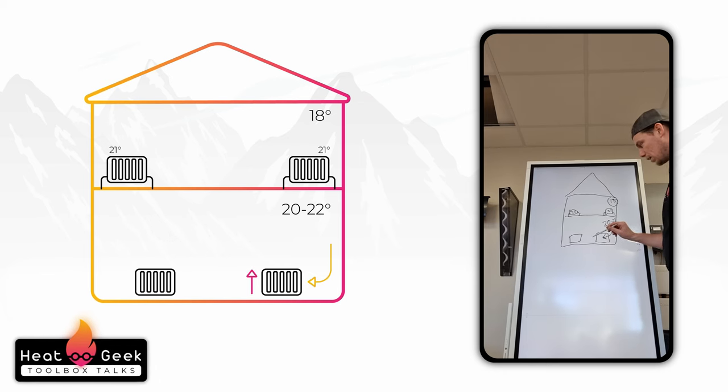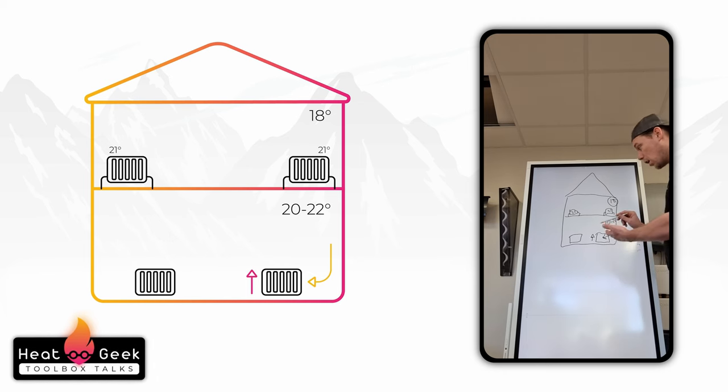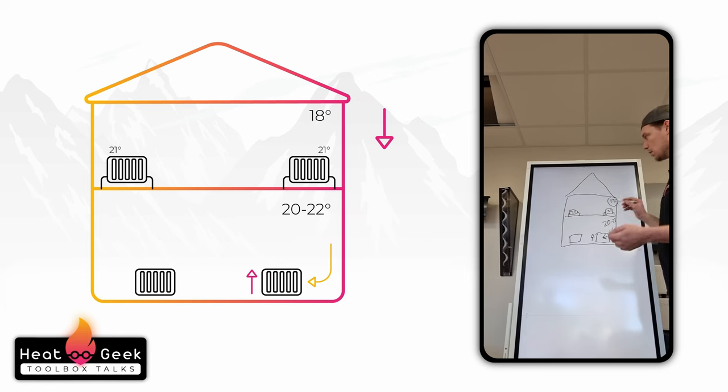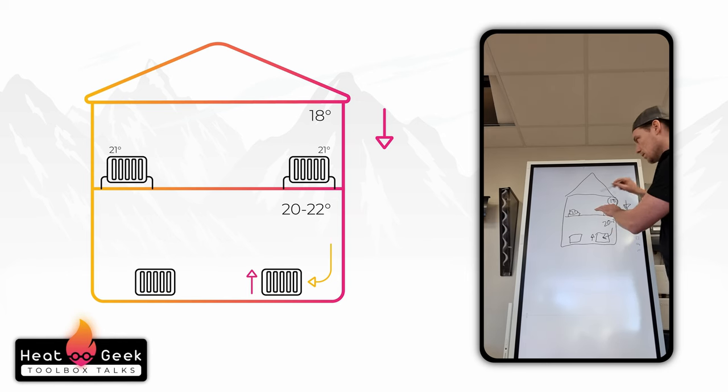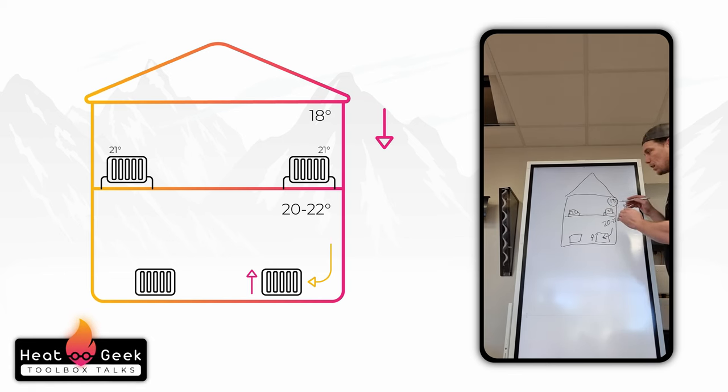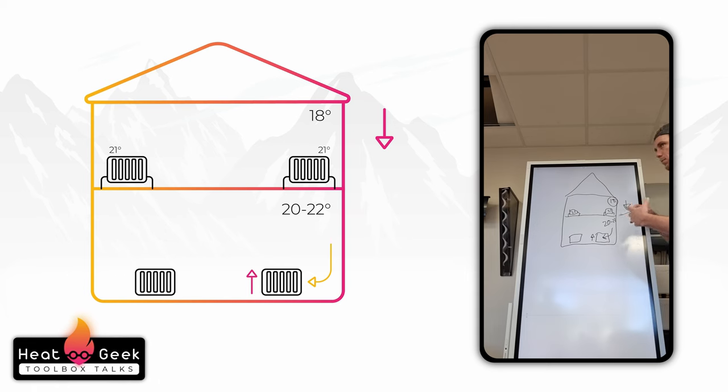That'll push more flow into these radiators. So the radiators in here will become a higher mean temperature. If they become a higher mean temperature, we get to drop the curve down on the heat pump and we increase COP. So we're reducing demand by dropping the flow temperature, and when it puts in less energy its COP increases.